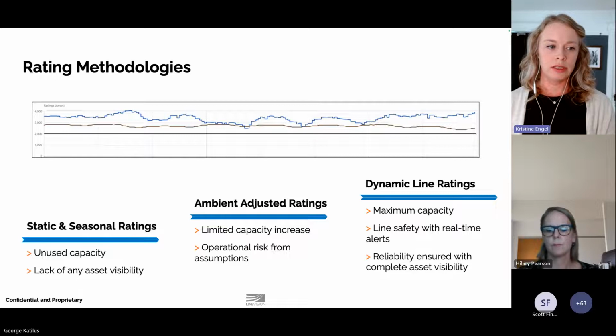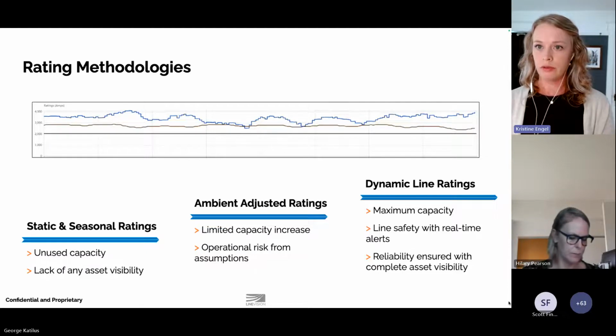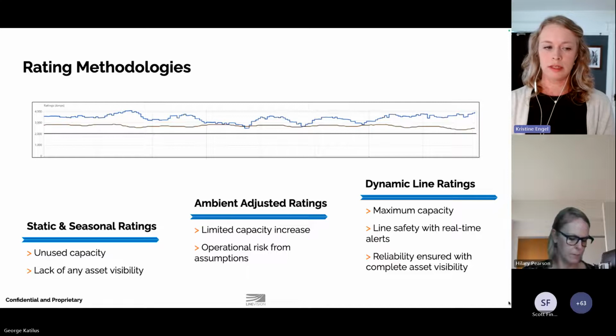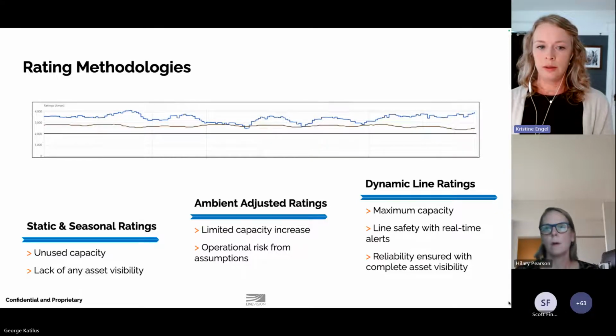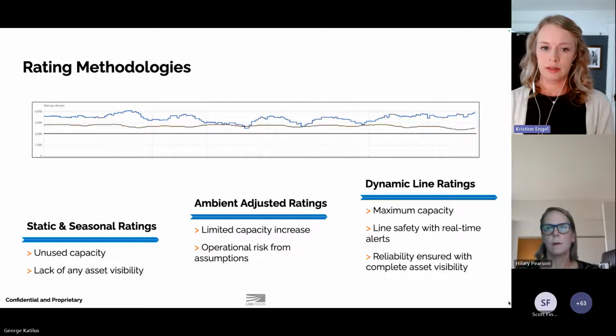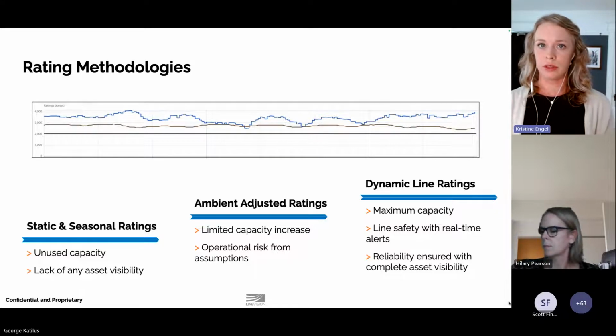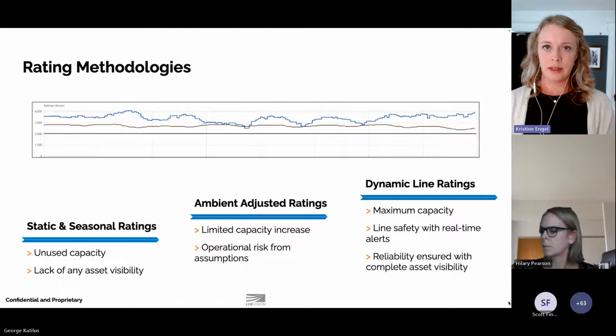When we use a static or seasonal static rating methodology, we're making assumptions about the ambient temperature across the entire year or season, as well as the wind speed. When we move up to ambient adjusted ratings, as required by FERC 881, we now vary the ambient temperature to get additional benefit from actual temperature information, but we're still using a fixed assumption of wind speed, and out of necessity that's usually a conservative value.